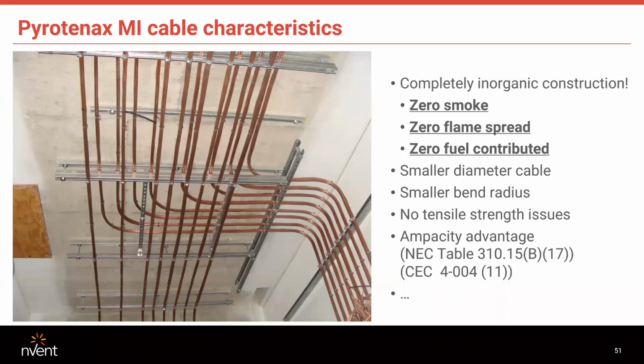But the big favorability with MI cable, and why it is far and away the most popular cable on the market, particularly with engineers, is that it's completely inorganic, gives off zero smoke, zero flame spread, zero fuel contributed to the fire. It's a smaller diameter cable. It's got a small bending radius. You can bend it, the size is 250 and smaller, up to 5 times the OD of the cable. And 350 and 500, you can bend 10 times the OD of the cable.